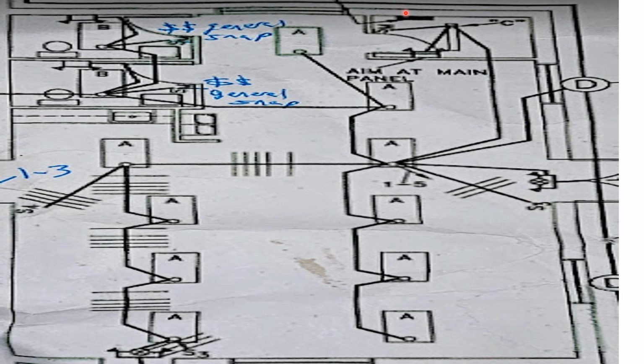So the first part of this circuit is from here to there. If I took out my ruler, I could measure on this set of plans, and I could estimate how much MC or EMT or whatever conduit or raceway that I'm using, I could measure it and see how many pieces that I need. So I'm going to write down sticks of conduit, the fittings that go in between. And this is just for one piece of this circuit. So I want to give you an idea of how to look at this, but this is how much, if you really want high quality estimates, this is what you really need to do. I start here at the panel. I'm going to pipe up and over. I come over here, and let's imagine that I've found out that it's 4 sticks of EMT. So I'm going to write down 4 sticks.